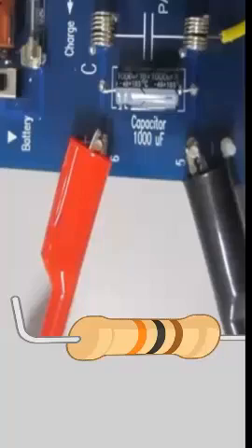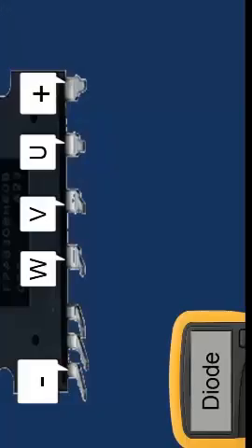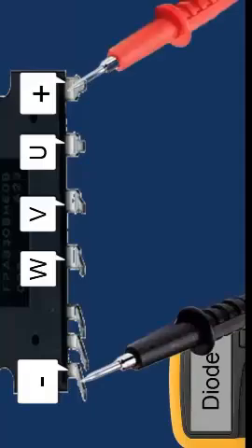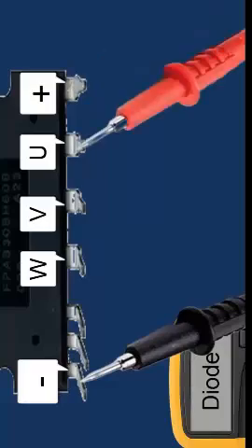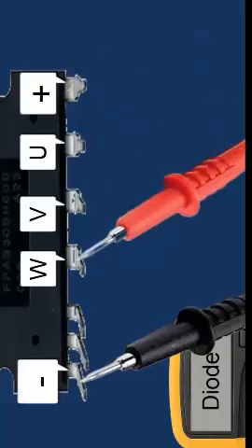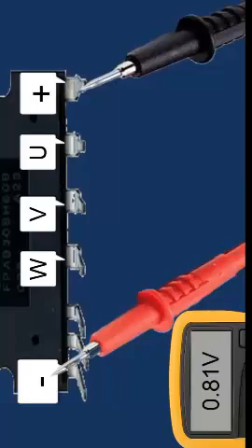General steps. Set the multimeter to diode mode. Place the black probe on the common terminal and the red probe on the positive. Test the negative pins and phases U, V, and W. There should be no reading.